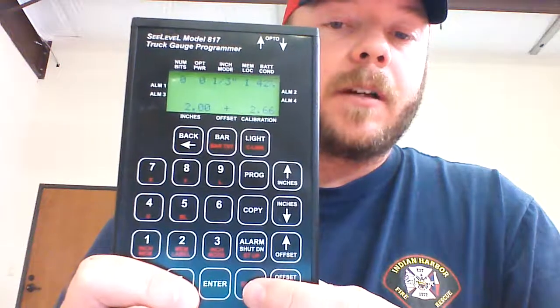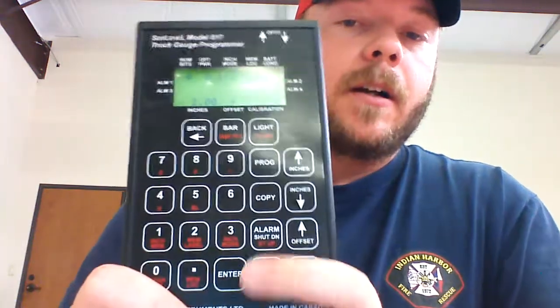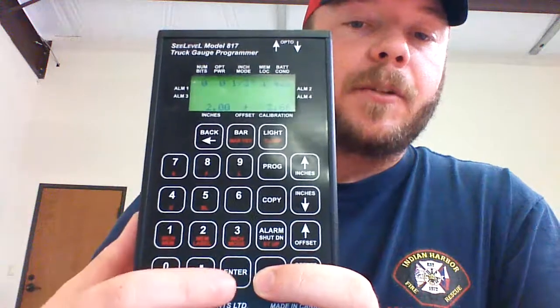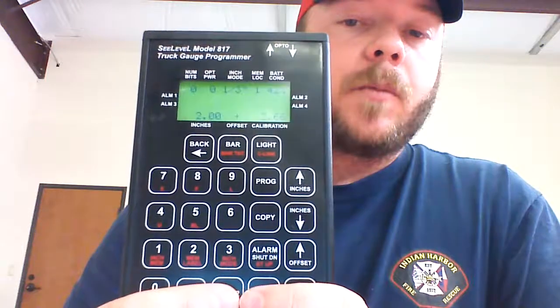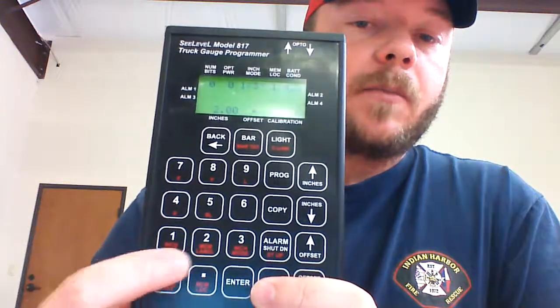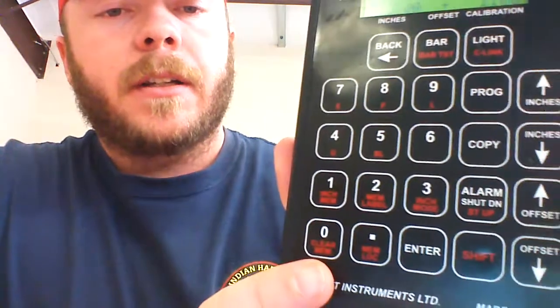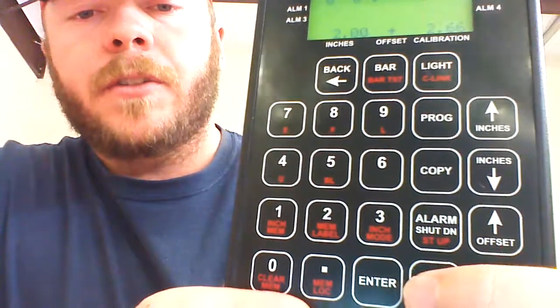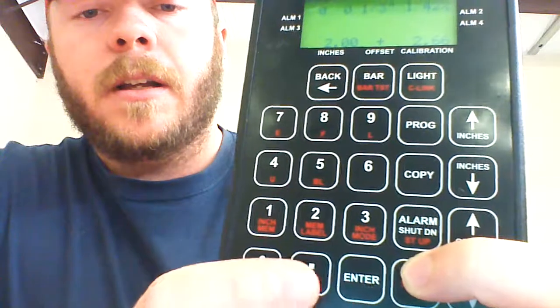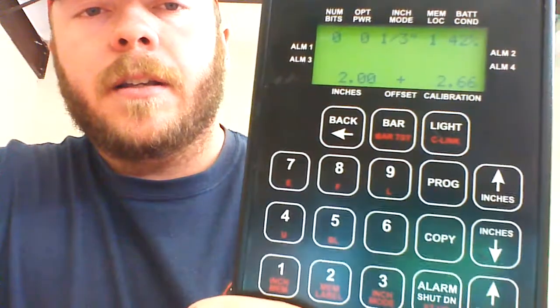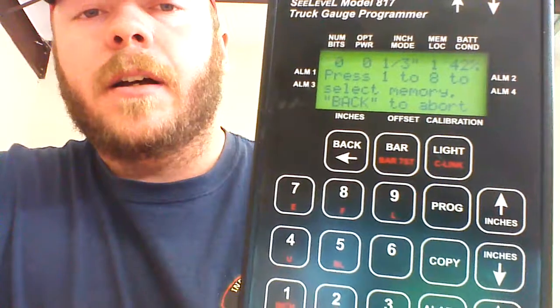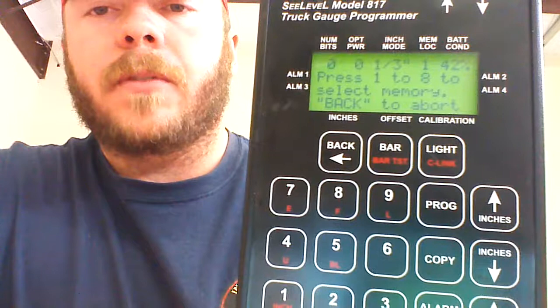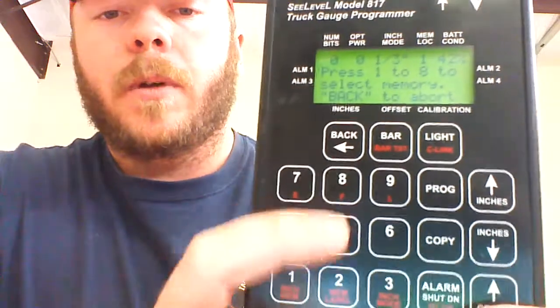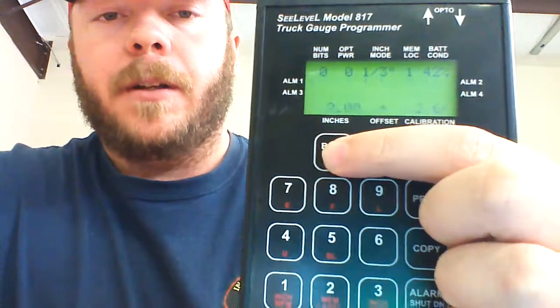We have our shift key here, which allows us to access the red letter menus. Our numerical keys here, our enter button, which will come in handy when we manually enter in a calibration. And then we have some red letter menus down here. If we wanted to change our memory location, we can hit the shift key and the mem loc, which is also the decimal point, and it's going to ask us to press 1 through 8 to select memory. So if we have different calibrations stored in different memory locations, we can access those there. Hit the back button to get away from there.